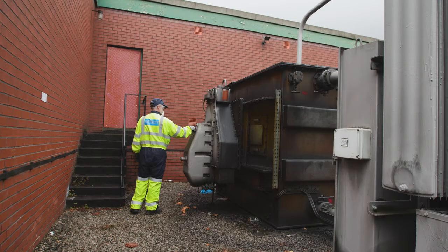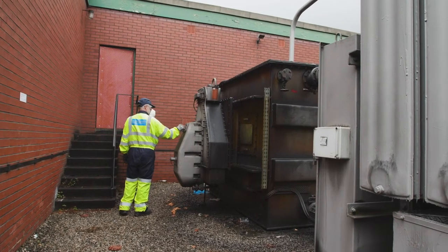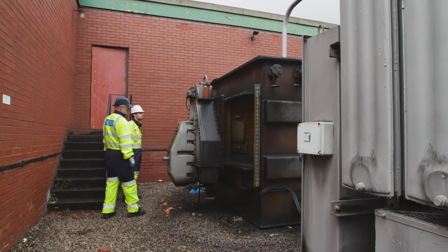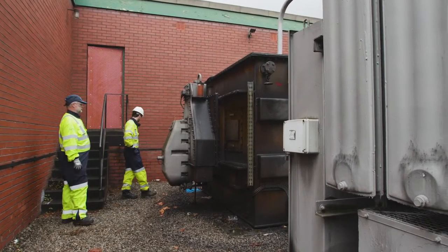That would mean switching out the unit, putting customers at risk for a significant period whilst we resourced specialist teams to come and carry out a repair. By using the tap changer monitoring, the plan is that we detect that in a sufficiently timely fashion that we can arrange the repair with the transformer still in service, so you reduce that period of risk to the customers, and equally we're not using those resources to go around and maintain units where there's still significant life in the tap changer before it requires this sort of maintenance.